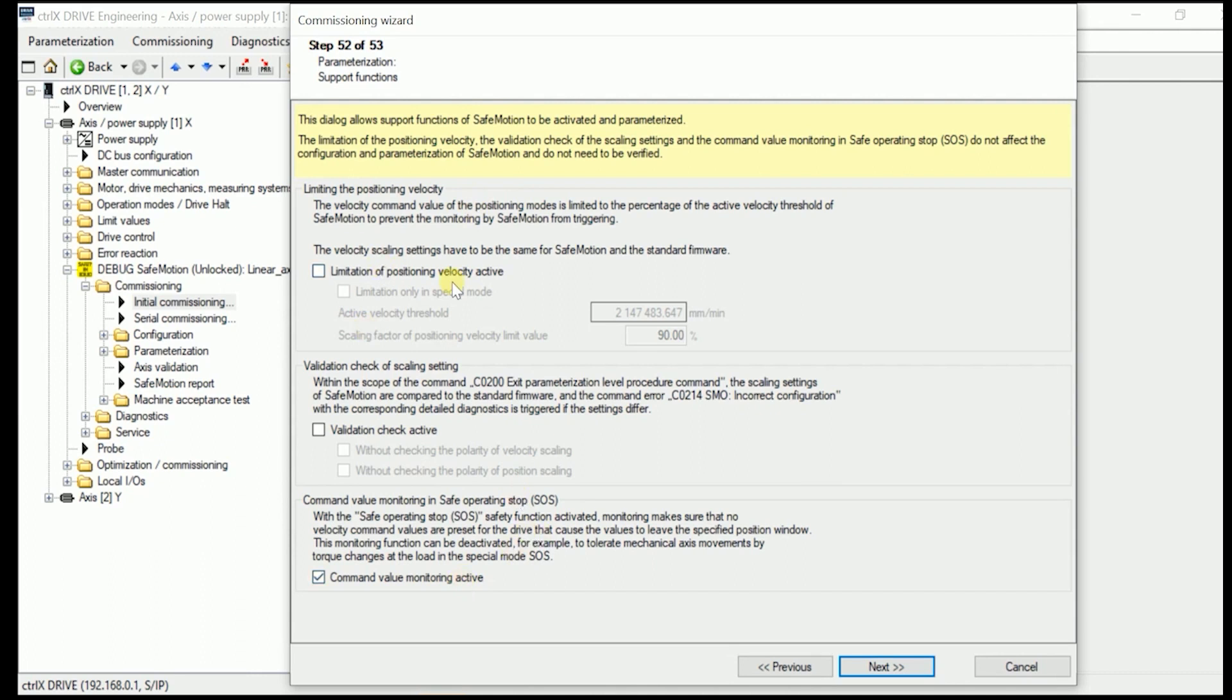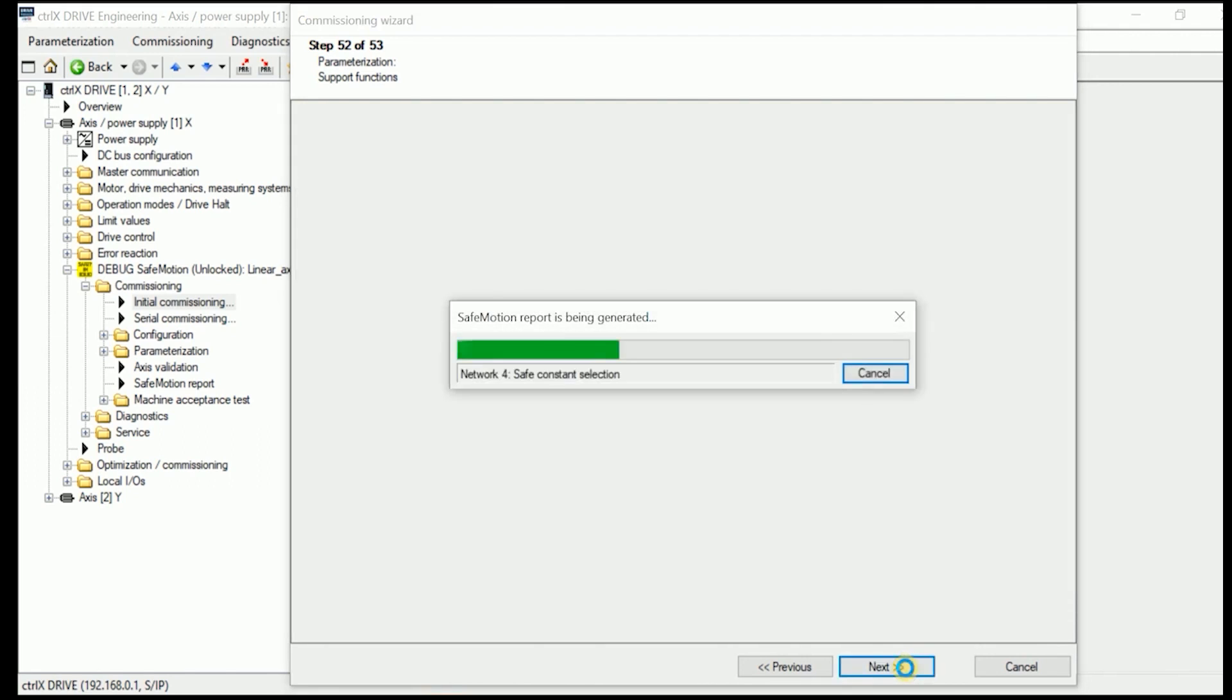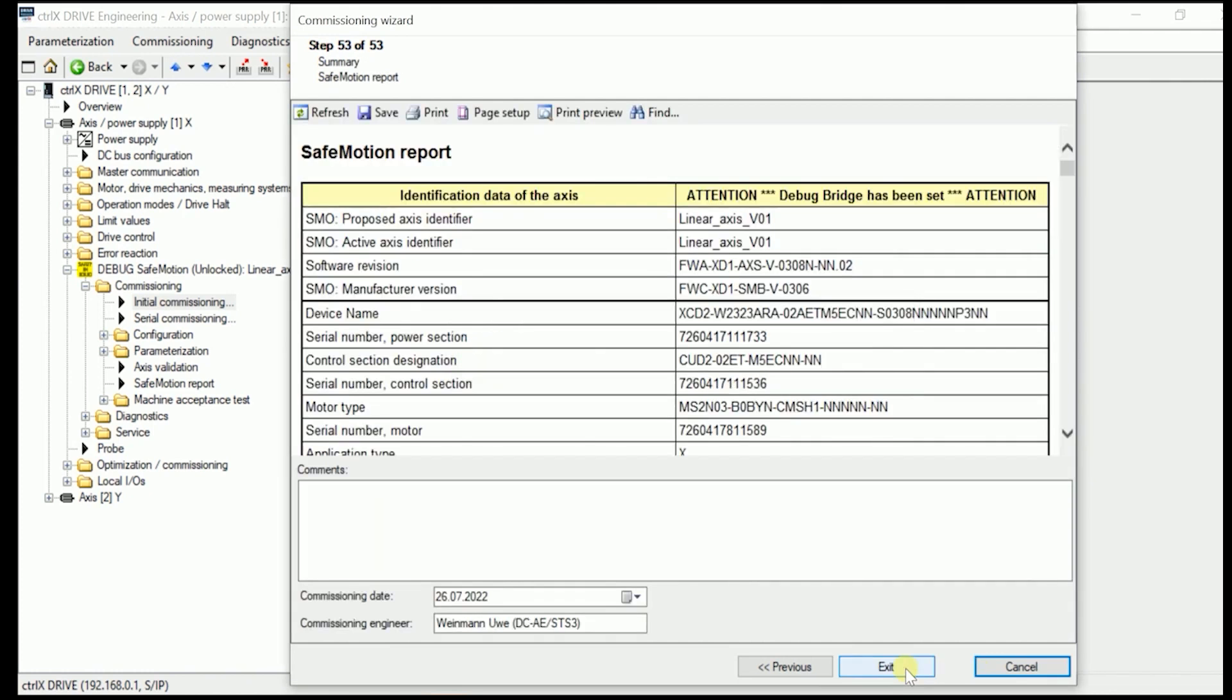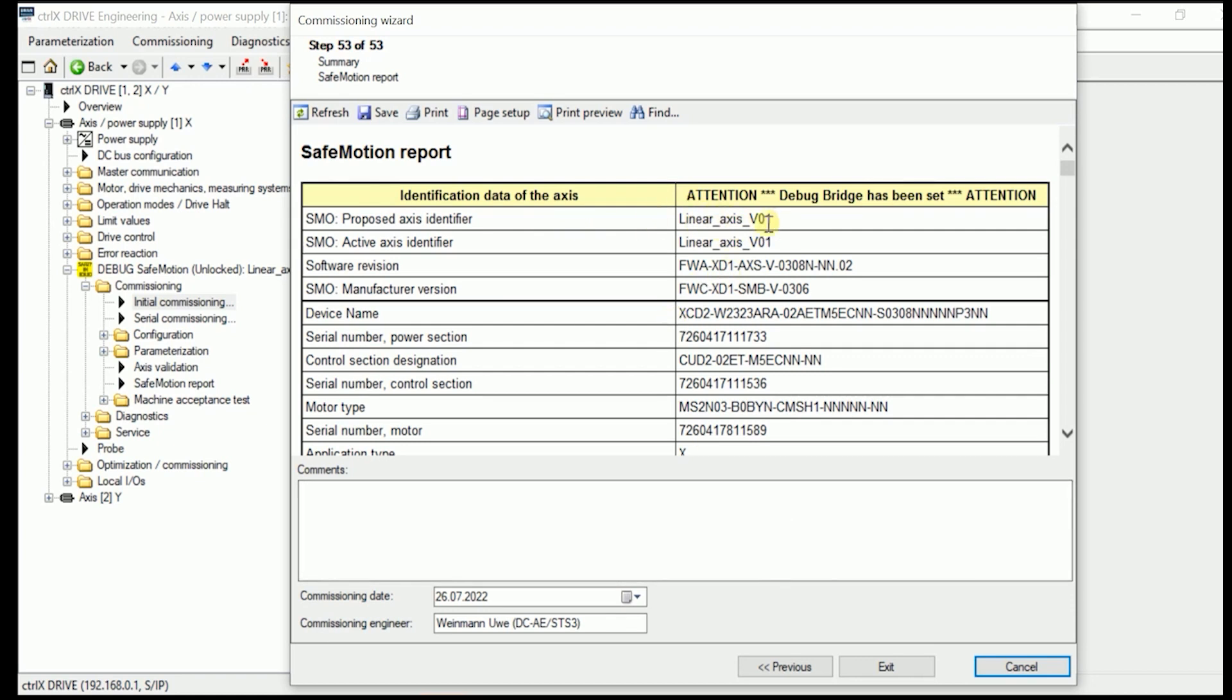Where we can select say the additional support functions. In here we leave everything except on the command value monitoring active. So that we have that we are done in here. Now automatically the safe motion report is being generated. Which we can use later on to just copy once again the same parameters. But then of course with changed serial numbers. And it is recommended to put the safe motion report to your actual machine in order to tell, okay that were the axis which is now identified in here with linear axis version 01.